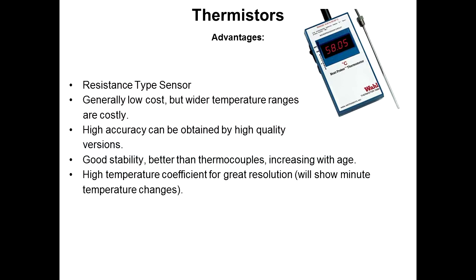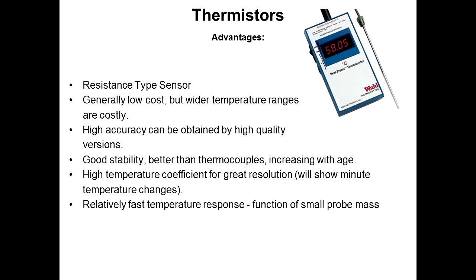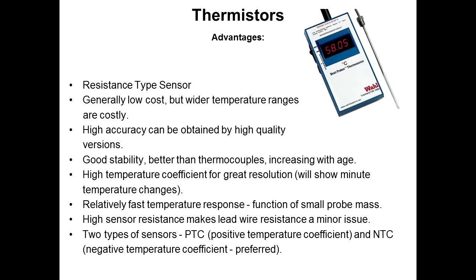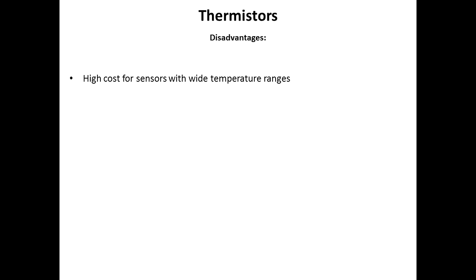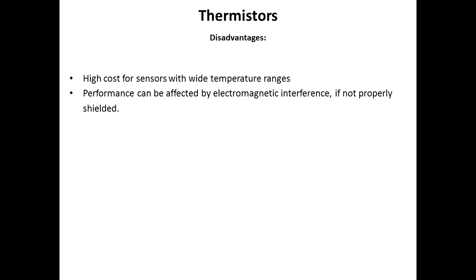High temperature coefficient for greater resolution. You get a very large resistance change with a minute temperature change, so it will show small changes. Pretty fast response, small probe mass. High resistance makes lead wire resistance a minor issue, so you don't have to worry about that. We talked about positive temperature coefficient, negative temperature coefficient. High cost for sensors if you have a very wide temperature range. They're generally used for low temperature applications. They can be affected by electromagnetic interference if not properly shielded.